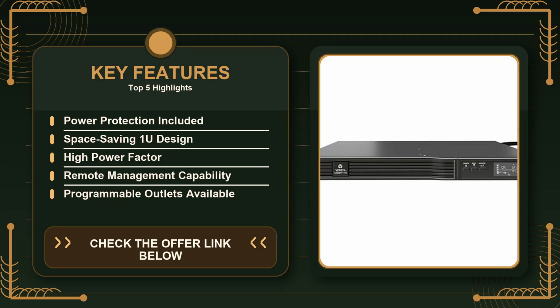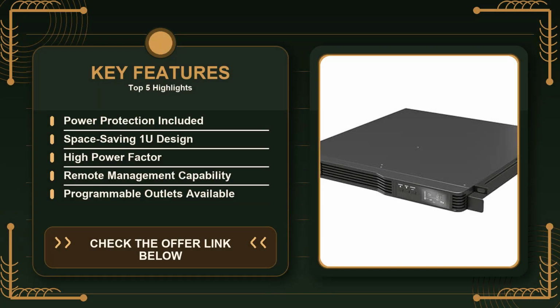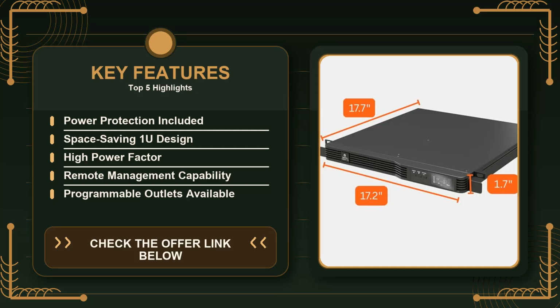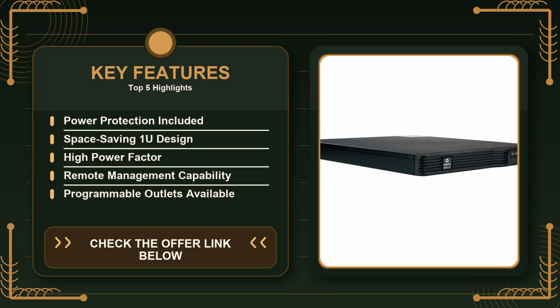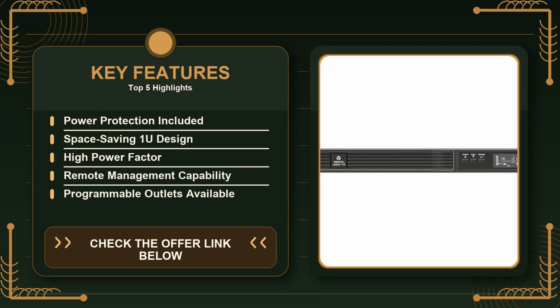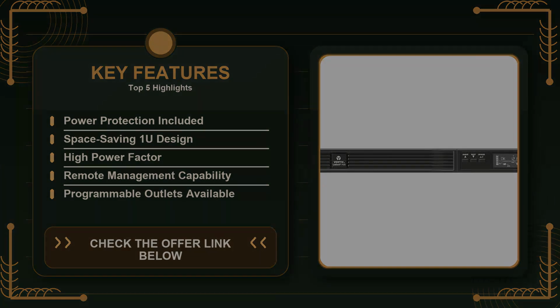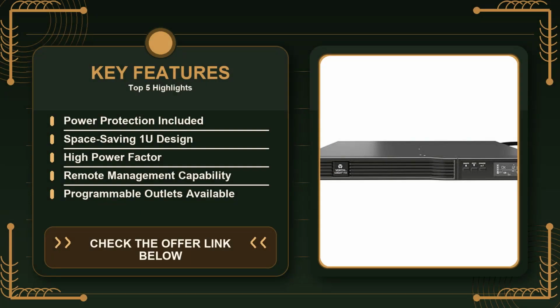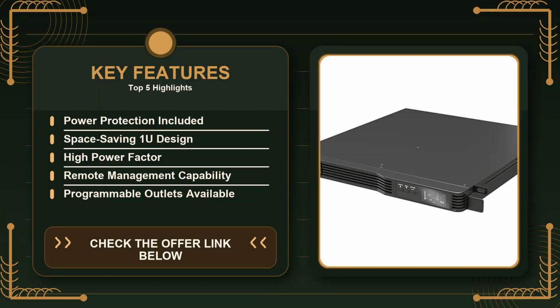The front panel is clean and the LED indicators give you an instant read on line, battery, and overload status without having to open the chassis. For admins who already use a remote management platform, the optional RDU 120 card means you can monitor load, battery health, and even perform graceful shutdowns via SNMP or the web interface. That reduces the need to walk up to the rack every time the UPS alarms, which is a genuine productivity saver. However, the trade-off for that compact size is the limited runtime on battery alone.